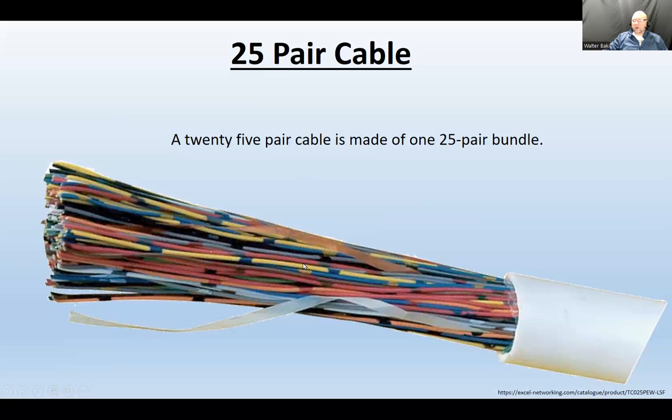One string or ribbon is going to go in a straight way through all the jacket. That's the rip cord. We could make a little nick here with the side cutters just to start the cut. Or if you pull hard enough and the jacket is manufactured in a way that it gives quickly, that rip cord is going to start the rip. And that's for basically stripping things further, because remember, when we score this, there's a chance that we damage those conductors.